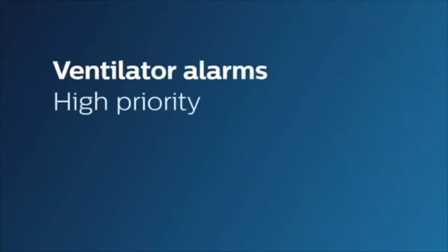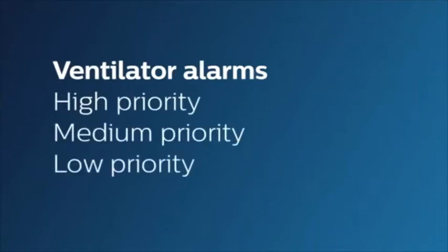Trilogy 100 provides continuous or intermittent ventilatory support. So it is very important that it operates correctly and without interruption. To alert you to issues with the equipment or with the patient's breathing, the ventilator has a number of alarms. Make sure the volume of the device is turned up loud enough so that you can hear these alarms clearly over other room or equipment noise. The ventilator has 3 types of alarms: high priority, medium priority, and low priority. The sound and visual cues help you recognize the urgency. In addition, informational messages and confirmation alerts notify you of conditions that may require attention, but are not alarms.